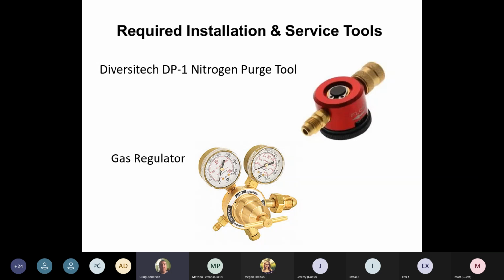So make sure you have a nice purge tool. You don't have to play with the regulator that's on the bottom. As long as you have 50 PSI of gas in it, this will regulate what you need to go through it. So there's no setting, just turn the nitrogen tank on and away you go. Nice little tool.